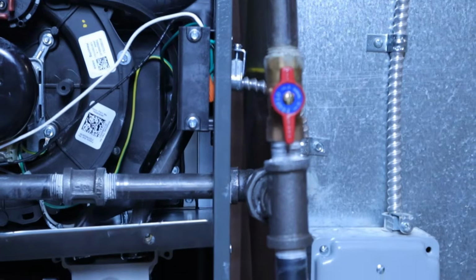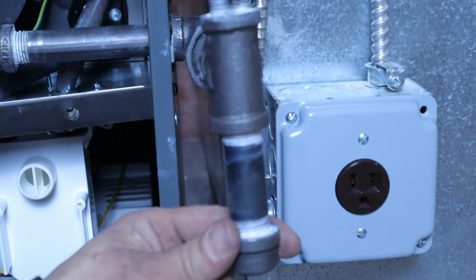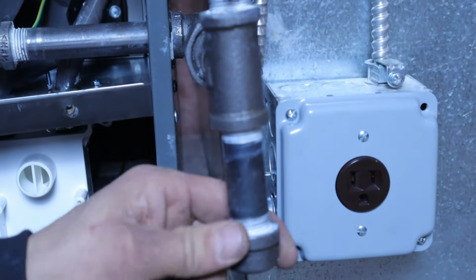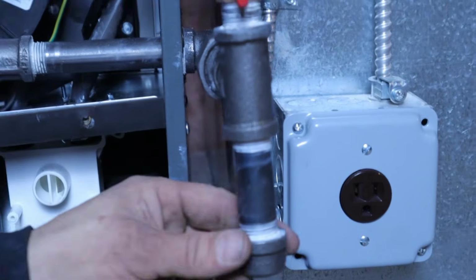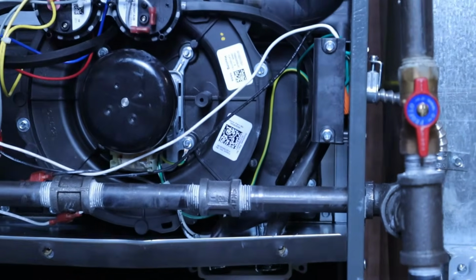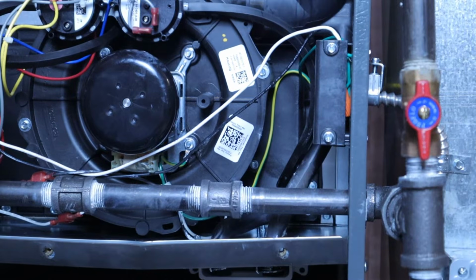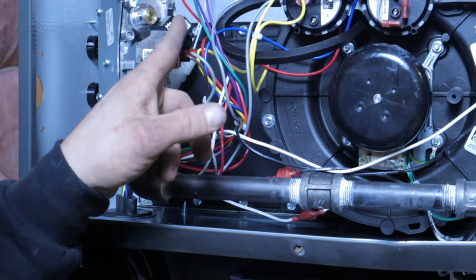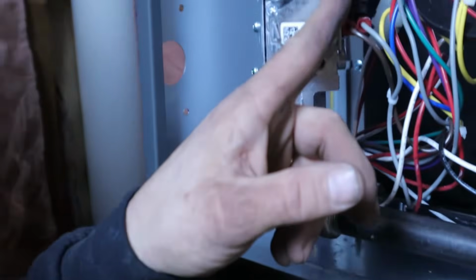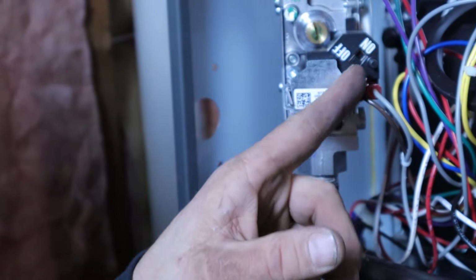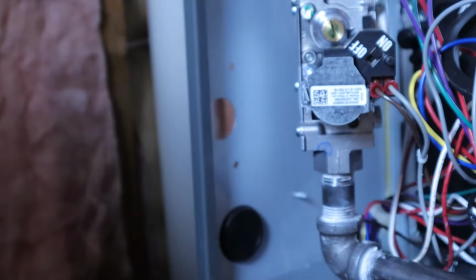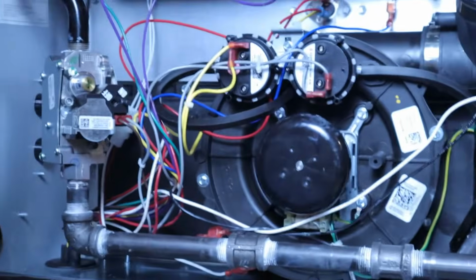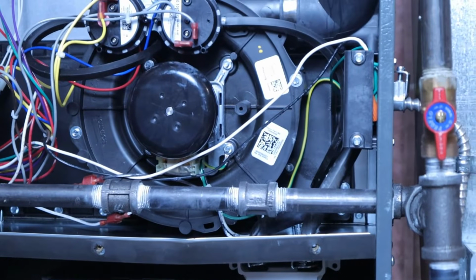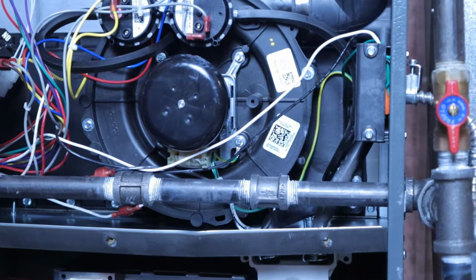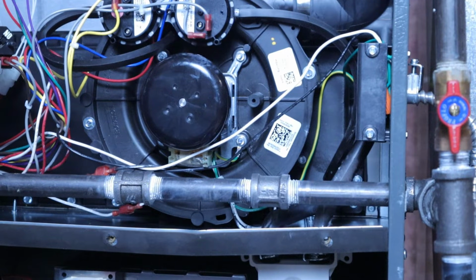We loosen the cap up down here, let a little bit of gas out just to get the air out of the line. Then we tighten it back up again, and you always want to make sure you've got a switch here on your gas valve in the on position. So we turn that on, and now our high voltage and our gas is all hooked up. Now we're going to hook up our low voltage and start running our drain lines.